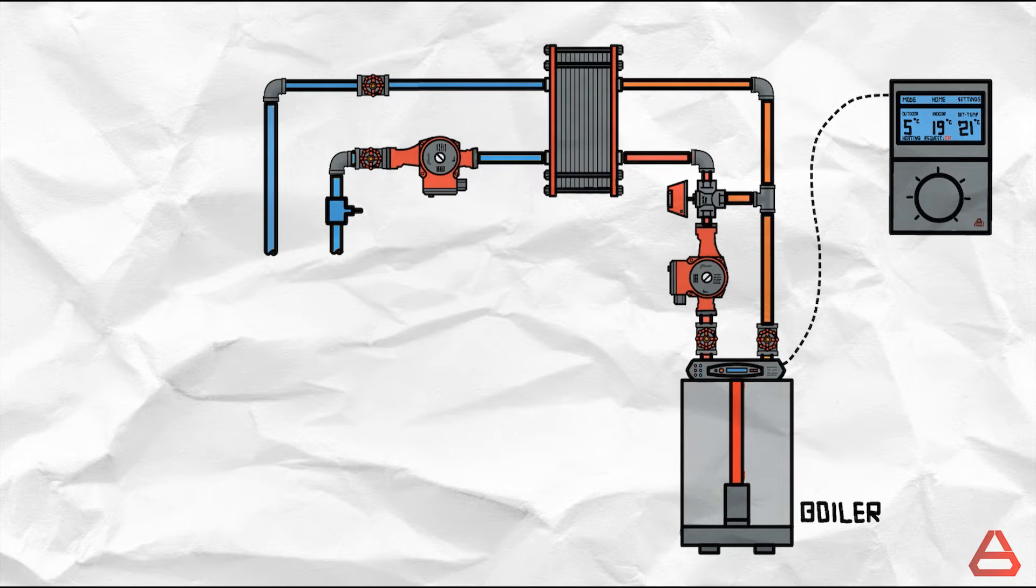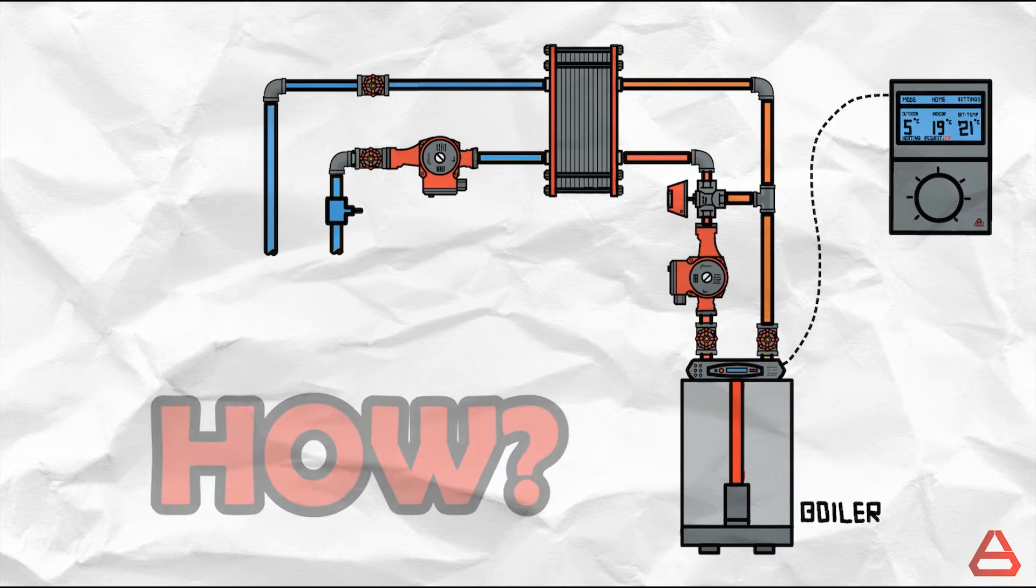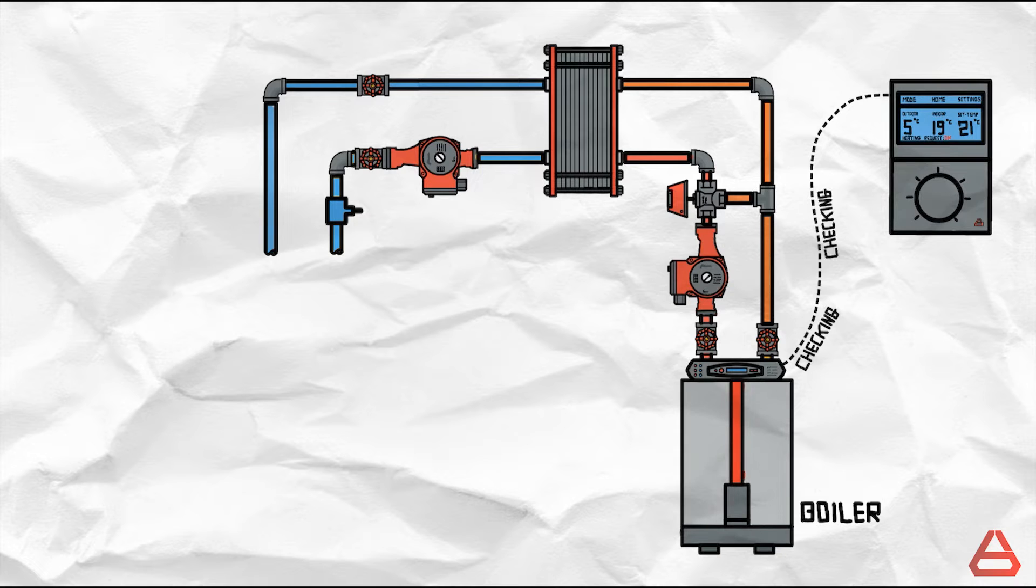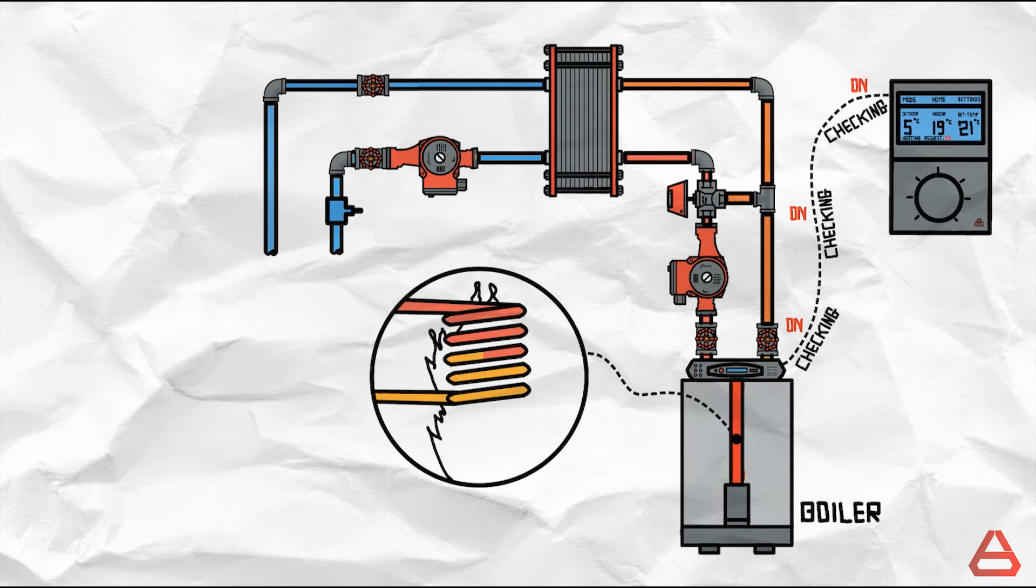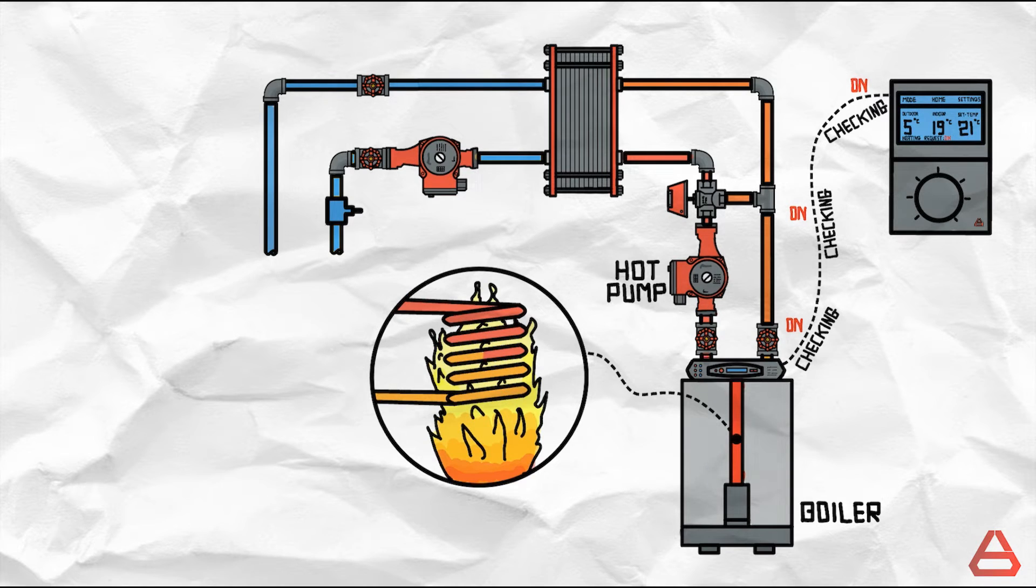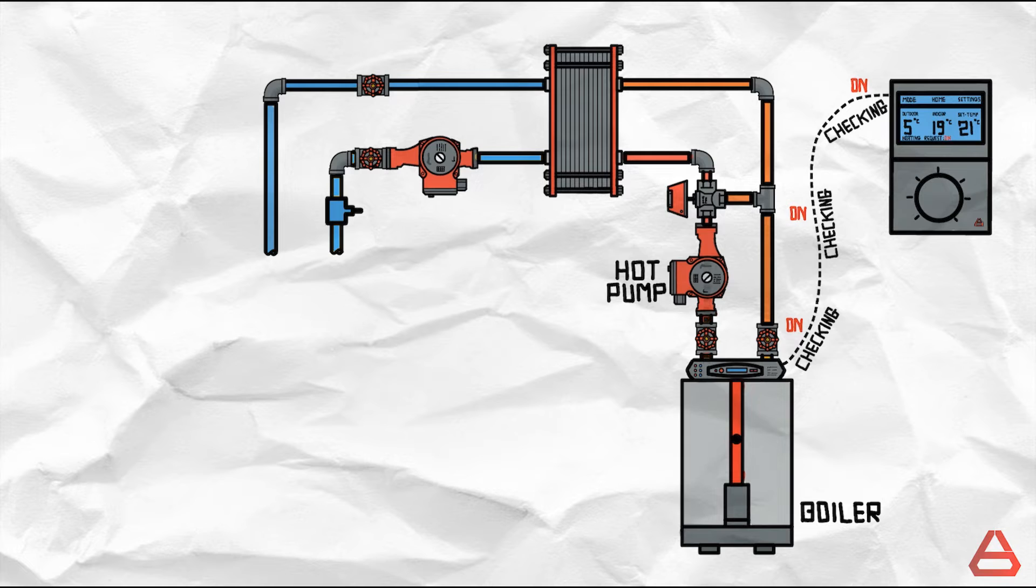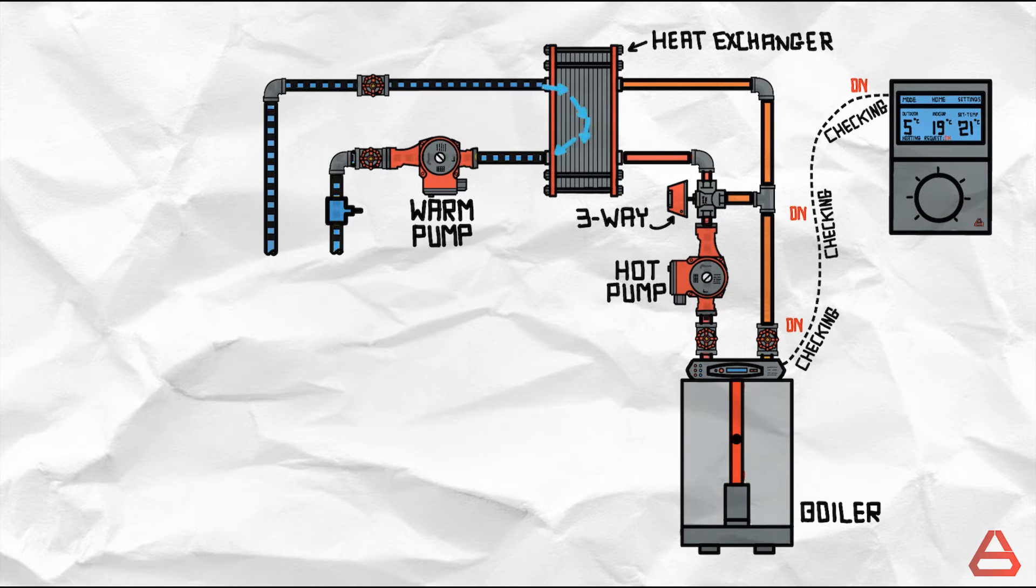So as we did for the heating circuit let's check out how this subsystem operates. The boiler begins by checking for a demand for heating that can be triggered by any of the room thermostats. If triggered it will ignite and begin heating the water while the hot pump is running and circulating the water. The water reaches the three way valve. At the same time the warm pump, still cold at the moment, is also running and circulating water through the heat exchanger and the warm circuit.